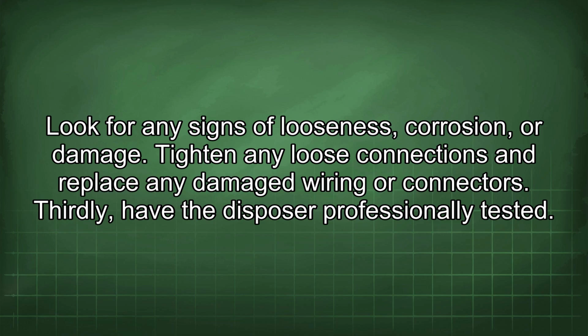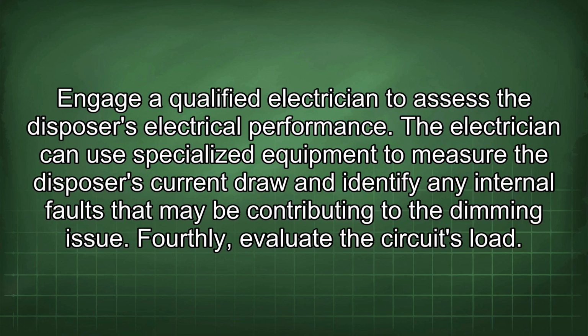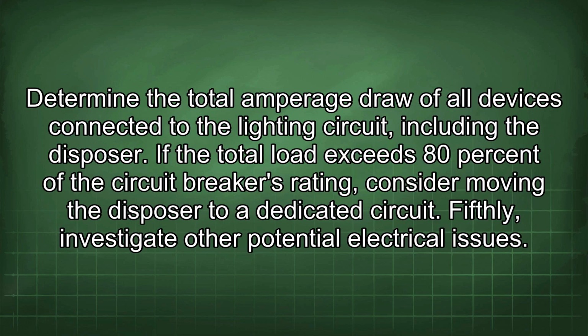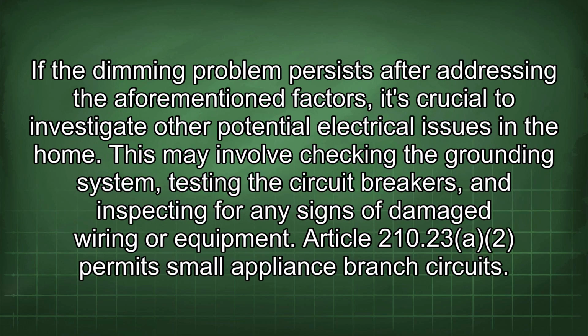Thirdly, have the disposer professionally tested. Engage a qualified electrician to assess the disposer's electrical performance. The electrician can use specialized equipment to measure the disposer's current draw and identify any internal faults that may be contributing to the dimming issue. Fourthly, evaluate the circuit's load. Determine the total amperage draw of all devices connected to the lighting circuit, including the disposer. If the total load exceeds 80% of the circuit breaker's rating, consider moving the disposer to a dedicated circuit. Fifthly, investigate other potential electrical issues. If the dimming problem persists after addressing the aforementioned factors, it's crucial to investigate other potential electrical issues in the home. This may involve checking the grounding system, testing the circuit breakers, and inspecting for any signs of damaged wiring or equipment.